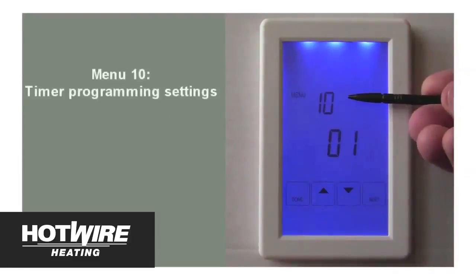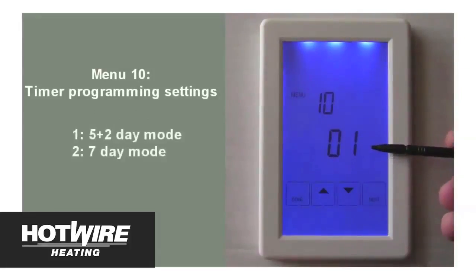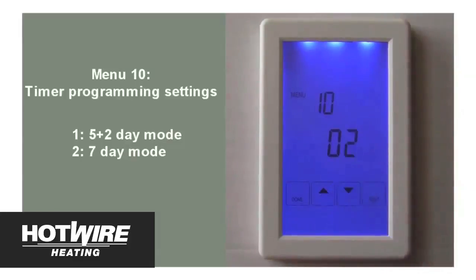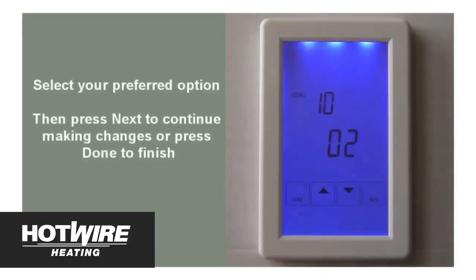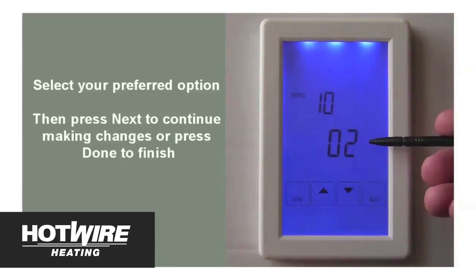Menu 10 is related to programming the timer and allows you to select between two programming options. Option 1 is called 5 plus 2 day mode, which will allow you to program the unit's switch on and switch off times just once, and they will be applied from Monday to Friday, with separate times to be programmed for Saturday and Sunday. Option 2 is called 7 day mode, which will allow you to set the switch on and switch off times for just one day, and they will be applied across the entire week from Monday right through to Sunday. In this case, we will use option 2, which means we will be given the option to set the switch on and switch off times for one day, and all other days of the week will use these exact same times.